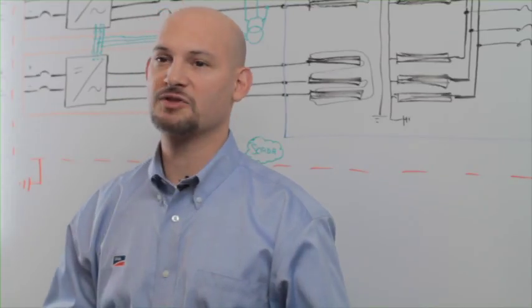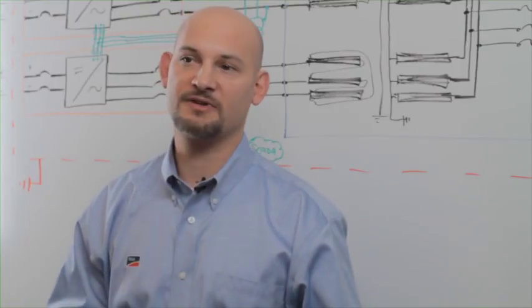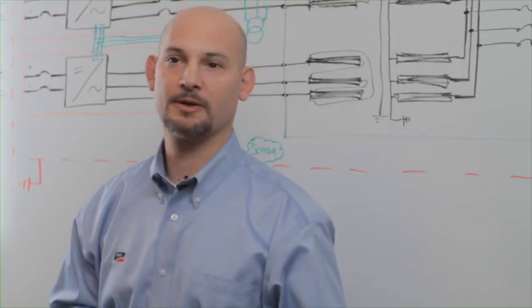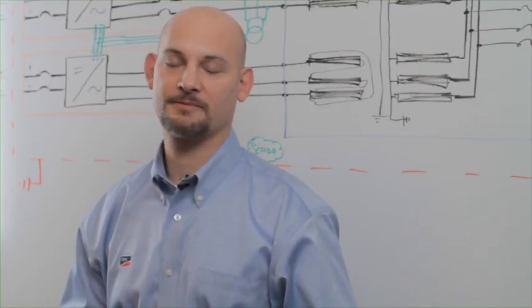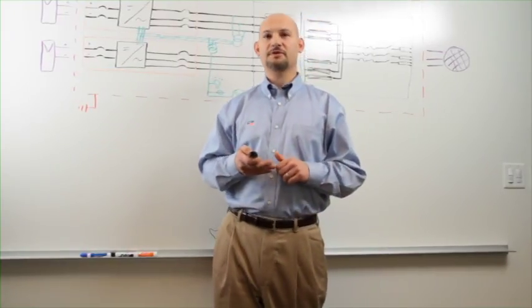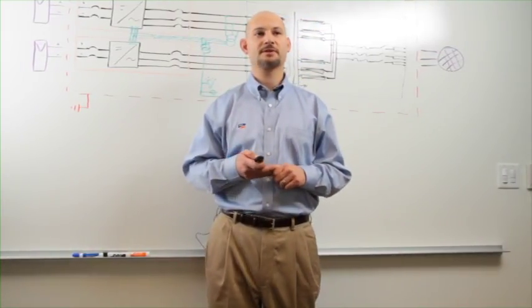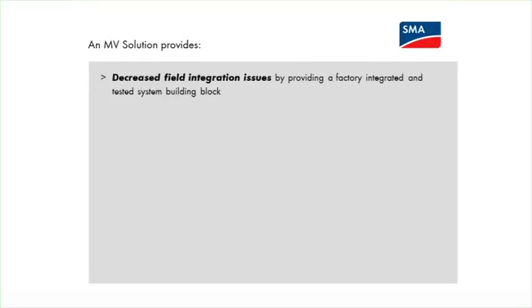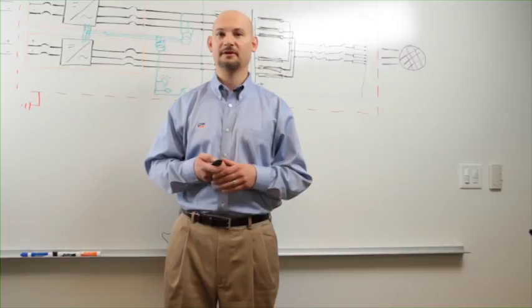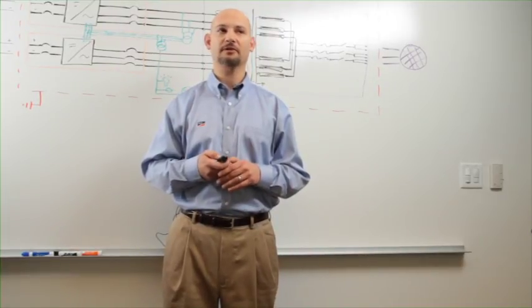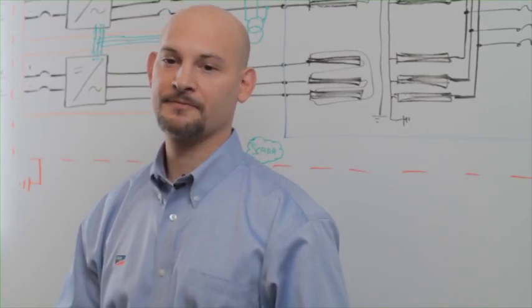So we typically have 2 inverters in a station feeding into a medium voltage transformer, which feeds into the point of interconnection. The benefit of a medium voltage solution to our customers is really a number of things. This includes decreased field integration costs, decreased quality excursions that could result from just the repetitive connection in the field and outside of a factory environment.